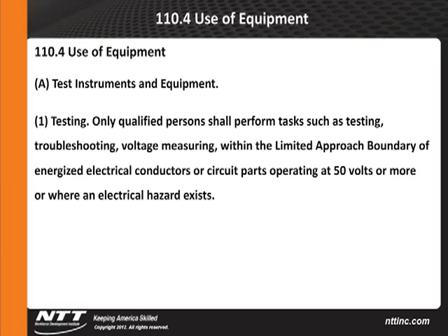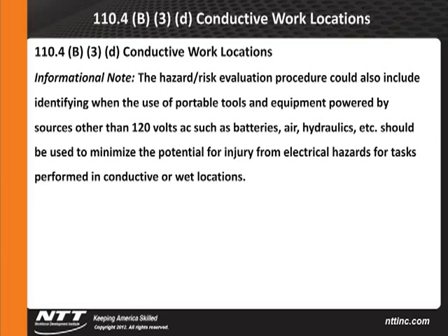Conductive work locations, new language again, important note. The hazard risk evaluation procedure could also include identifying when the use of portable tools and equipment powered by sources other than 120 volts AC, such as batteries, air, hydraulics, etc., should be used to minimize potential for injury from electric hazard for tasks performed in a conductive or wet work location. So what is a conductive or wet location? Well, by definition, that's any electrical equipment mounted inside or outside subject to water or moisture.